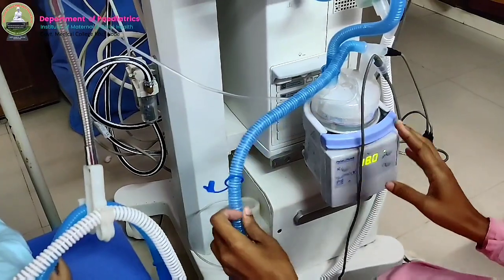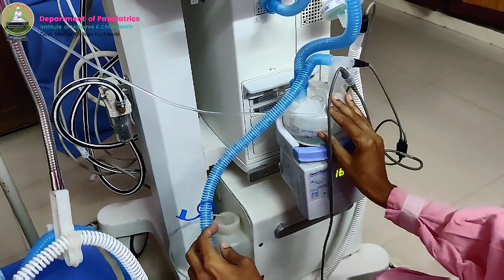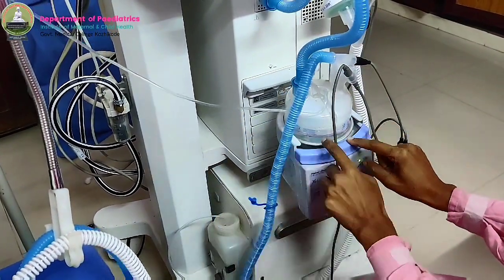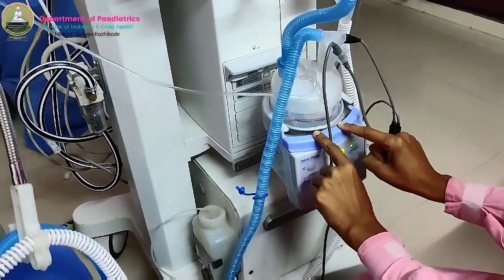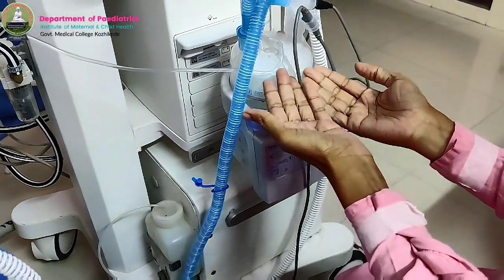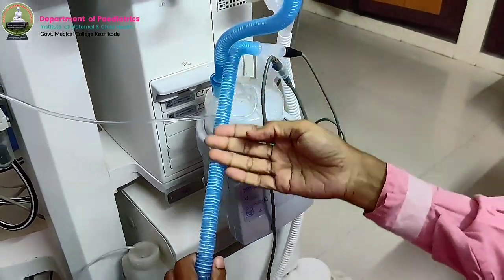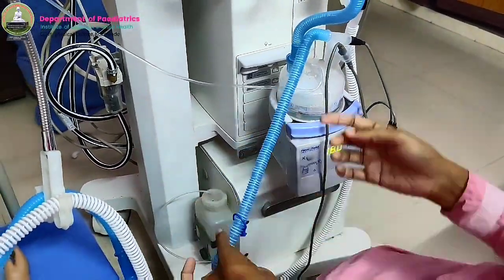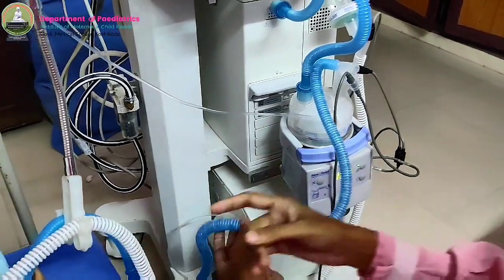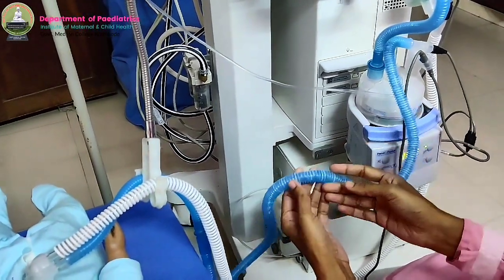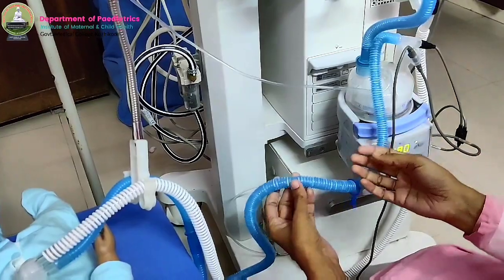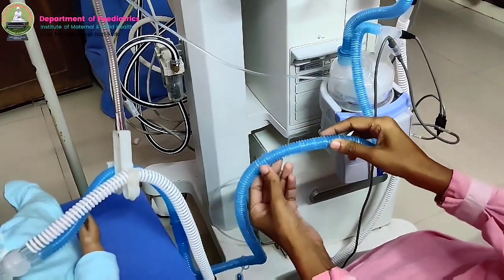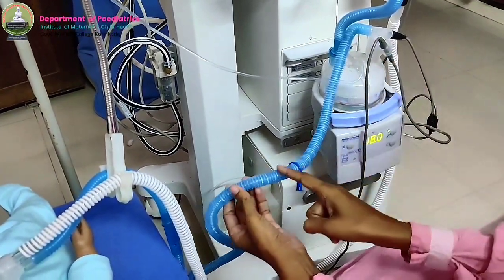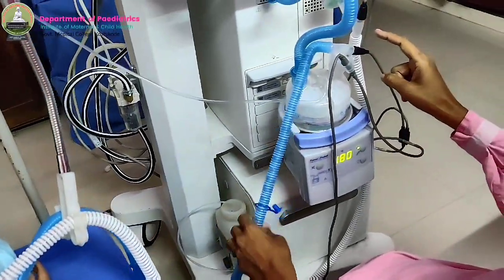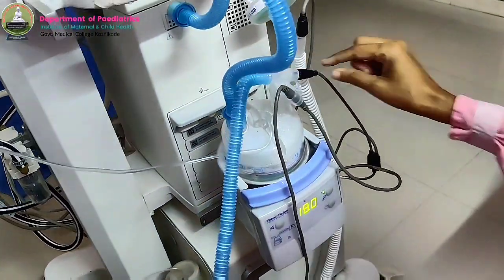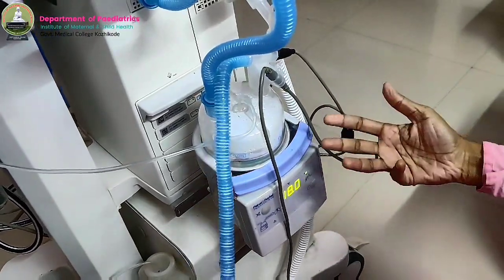Here the humidification occurs mainly from the humidification chamber by heating the base of this humidifier. Water vapor will be produced here and it will be carried through the circuit to the patient. By the time it reaches the patient end, some of the heat will be dissipated and water vapor will condense within the circuit. To avoid this, there is a heated wire. For that, we need a heating cord also. That I will explain later.